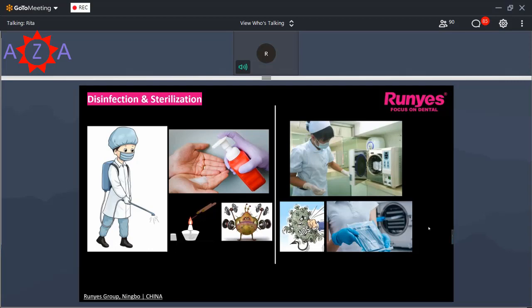According to the requirements of the technical operation specifications for disinfection of dental clinic instruments, a medical institution regulation formulated by the MOH and combined with the actual clinical situation, the appropriate disinfection or sterilization method should be selected according to the danger degree and the material characteristics of dental clinic instruments. All kinds of oral medical instruments that come into contact with wounds, blood, or sterile tissues of the patient, including the dental handpiece and needles, must be sterilized before use. So I think this is the difference between disinfection and sterilization, and why we need sterilizers.